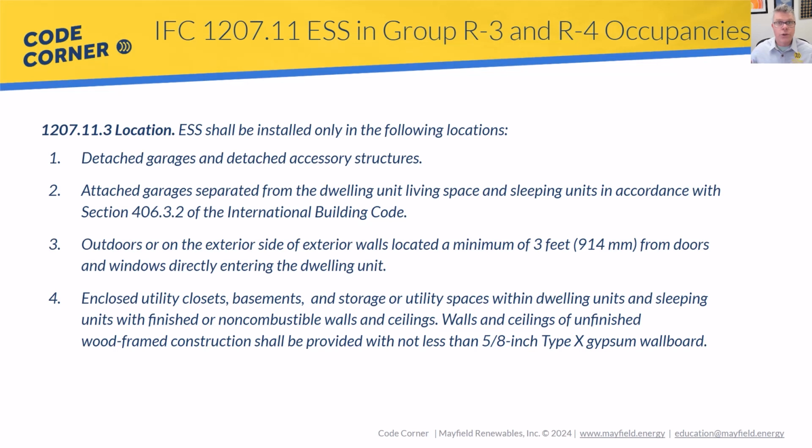And then moving on into the location, I'm not going to read all of these out to you, so if you want to hit pause on the video, take a minute to read these. But what it's getting into is just saying, here are the locations where you can install the energy storage systems. Again, residential focus on this one. And so we have multiple locations where we can put these, install them, and be in compliance. And we have a little bit of direction there. So you can see we can put them in garages, we can put them in outdoor buildings, we can put them outside. And so number 3 from that previous slide, where I was showing the 3 feet separation from the windows and doors, that's where we're getting that specific requirement for that separation.